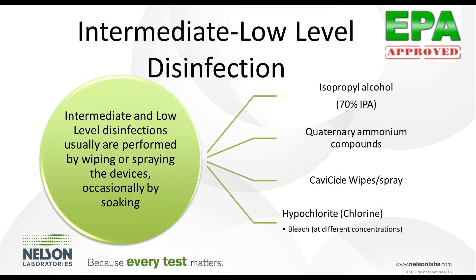When doing the disinfection validation, particularly in the U.S., you want to make sure the chemical is approved by the appropriate governing body. High level disinfectants are governed by the FDA, whereas low and intermediate level disinfectants are governed by the EPA. You would want to confirm your chemical appears on the appropriate approved list.